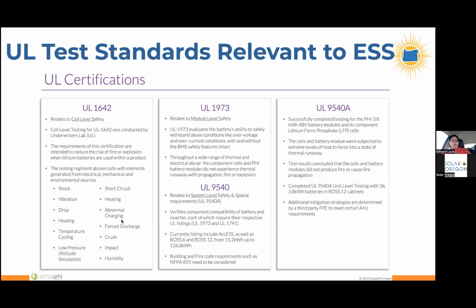Those similar tests are also done at the module level. When you put a bunch of cells together into a pack or a module, the UL 1973 test does those similar tests at the module level. And one of the things they test is whether the battery management system can successfully keep the battery pack safe, for example in a short circuit situation. And then also, what happens if that battery management system somehow fails catastrophically in a way that results in the cell pack being short circuited or charged beyond its safe limits? Then what happens to the whole cell pack? Those test methodologies are written out in UL 1973.